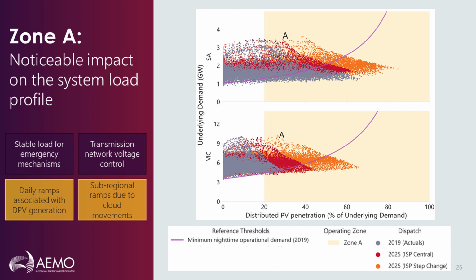Next is transmission voltage control. So reducing daytime load, as seen by the transmission network in locations with sufficiently large clusters of DPV generation, starts to impact how voltages are managed within the transmission system. The purple line on these charts traces out historical nighttime minimum demand levels. So we've shown this because voltage control challenges have historically occurred in the middle of the night when demand is very low and not much synchronous generation is online.